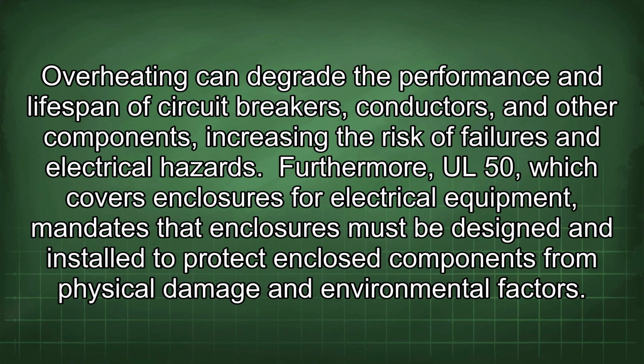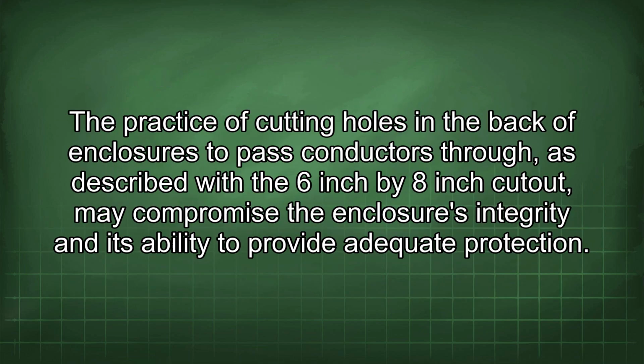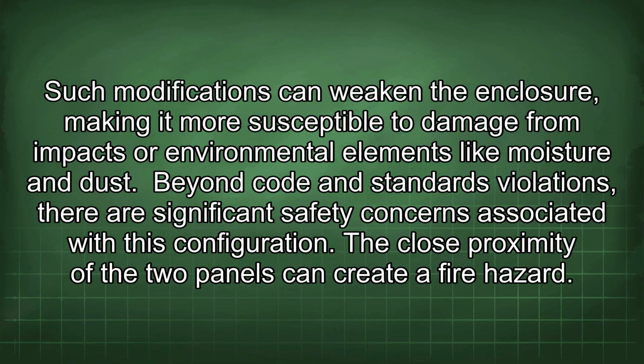Furthermore, UL 50, which covers enclosures for electrical equipment, mandates that enclosures must be designed and installed to protect enclosed components from physical damage and environmental factors. The practice of cutting holes in the back of enclosures to pass conductors through, as described with the 6-inch by 8-inch cutout, may compromise the enclosure's integrity and its ability to provide adequate protection. Such modifications can weaken the enclosure, making it more susceptible to damage from impacts or environmental elements like moisture and dust.